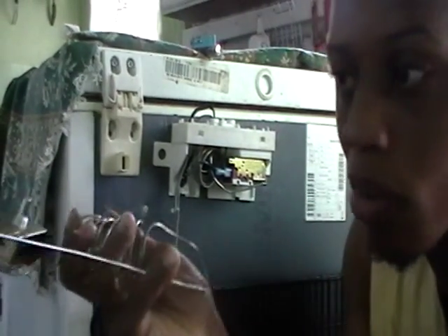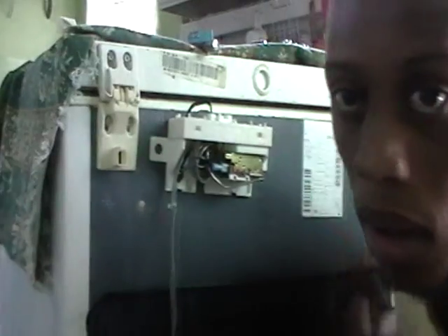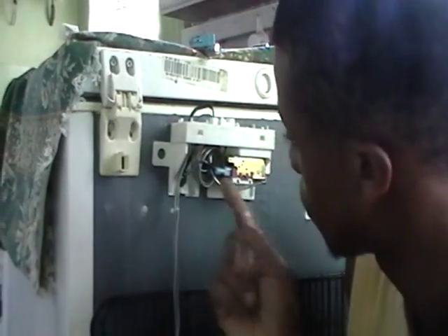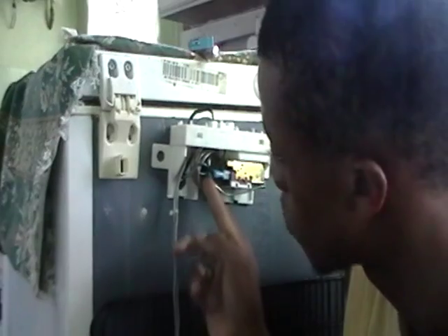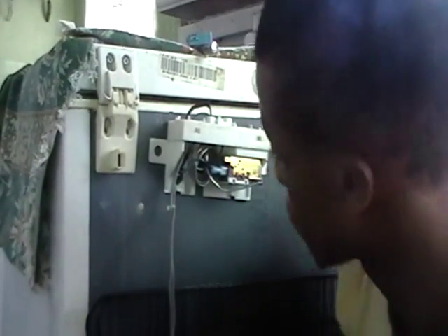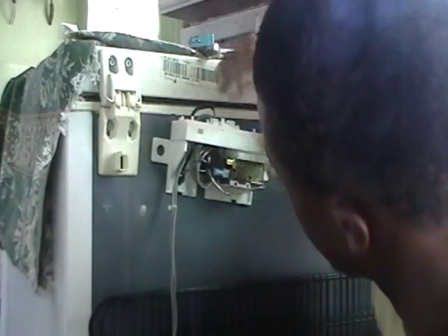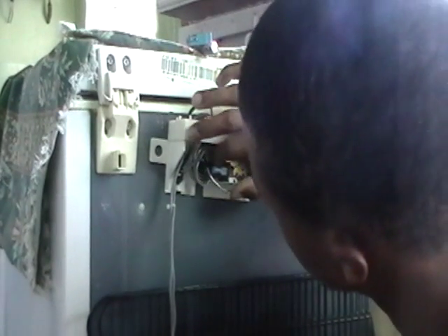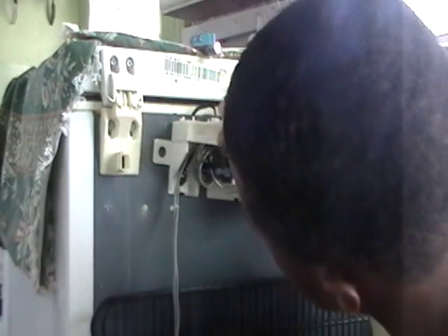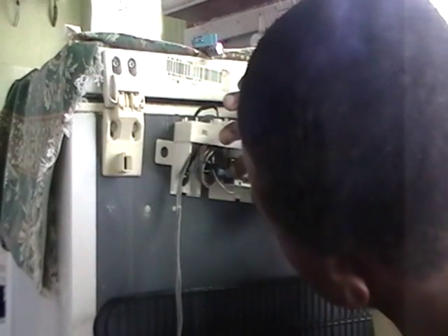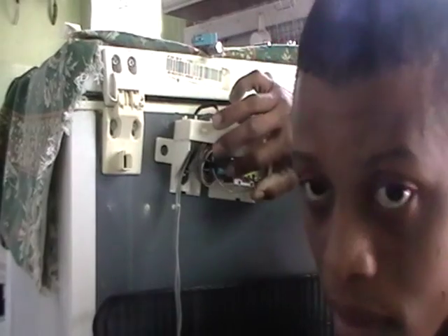Sorry I couldn't actually show you guys how I got it in, but all I did was route it back in just as the old one was. I fed the new one in, coiled the terminal probe, fit it in, tightened the set nut to hold the thermostat, and connected the two wires to two of the probes. I put an extra terminal here as an insulator since I won't need the extra probe, because as I said, this freezer doesn't have a light or extra auxiliary circuit.